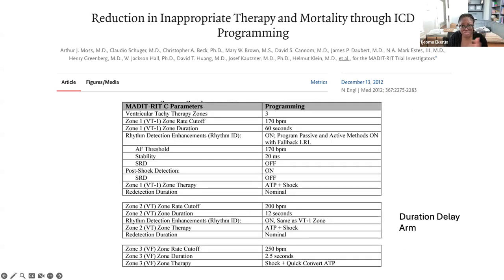to just see if the patient had VT at a lower rate. And then there was a duration delay arm where you had VT in all zones, but they delayed the duration of detection. So instead of the detection being 12 seconds, it was pushed out to 60 seconds. And then in your VT2 zone, or zone two, which was 200 beats a minute, that's when it went back to 12 seconds. You had an ATP and a shock.